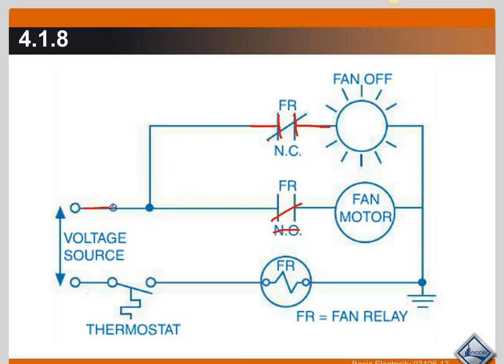We now have power that comes through this closed contact to the fan motor. Fan motor is operational. We have power that comes up here to the fan relay normally closed contact which is now open because this fan relay is energized and the fan off light is now off.